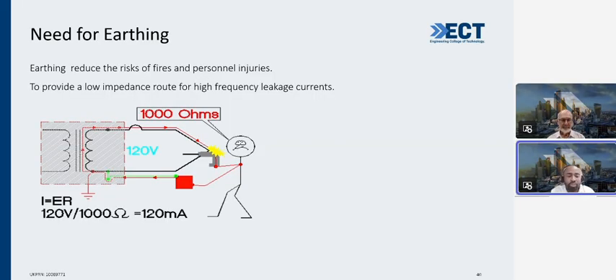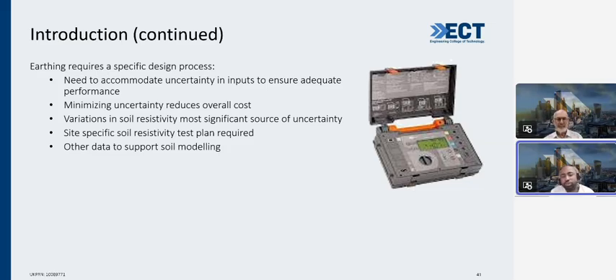One of the important things when it comes to earthing is the earth termination rods, or the earth rods. They have to be of high-grade electrolytic copper to provide that conductive path. I saw someone mention the IEC standard 62305, and I think it's also IEC 62561, which speaks of the types of rod: it has to be conductive, and its inner core of high-strength steel has to be strong enough to be driven into the ground. Yeah, so I'll hand it back to Steve.